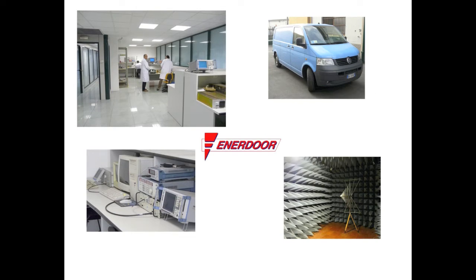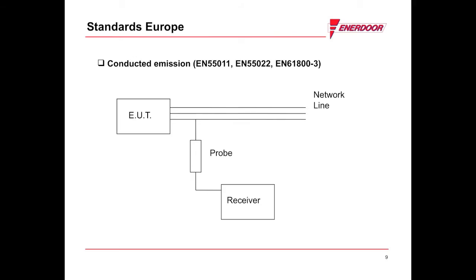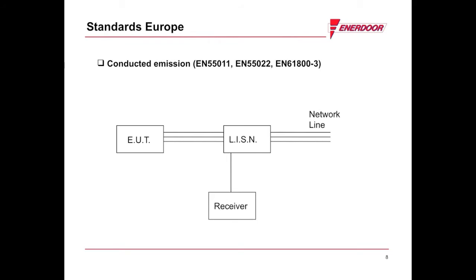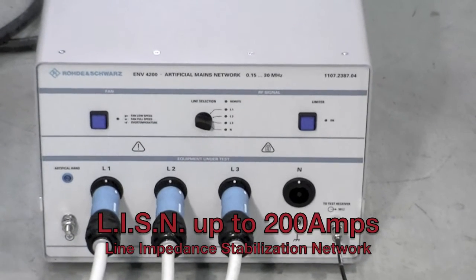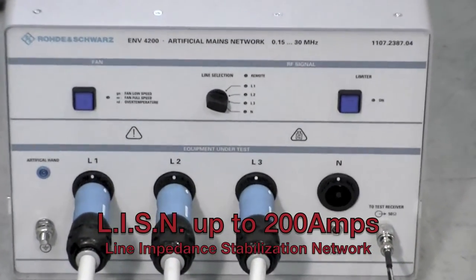Enerdoor provides testing services which can assist you in finding the correct EMI RFI filter for your machine. Enerdoor has over 15 years of experience in EMC testing. Enerdoor uses an RF receiver and probe to measure the noise generated by the machine's drives, as well as a line impedance stabilization network used to decouple the main line disturbances and measure only the electromagnetic noise generated by the machine.